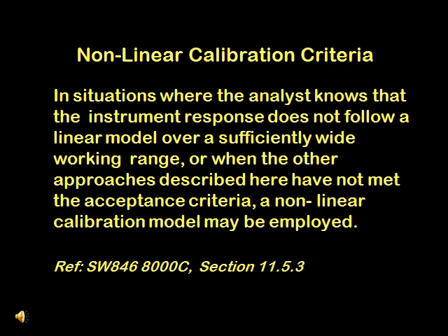8000C has also inserted the following cautionary note that a nonlinear calibration model may be employed if the following steps have not resulted in an acceptable linear curve. 1. Changing instrument operating parameters. 2. Reanalyzing the problematic calibration standard. 3. Narrowing the calibration range by dropping or replacing end standards. And 4, the analyst knows that the instrument response does not follow a linear model over a sufficiently wide working range.